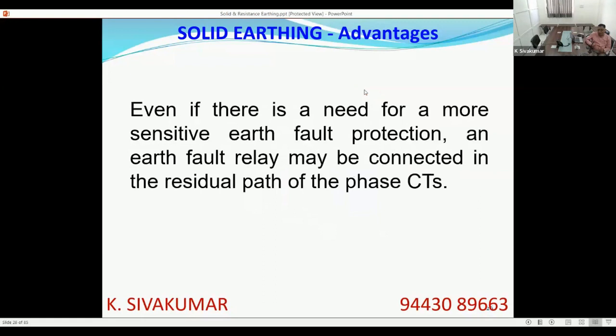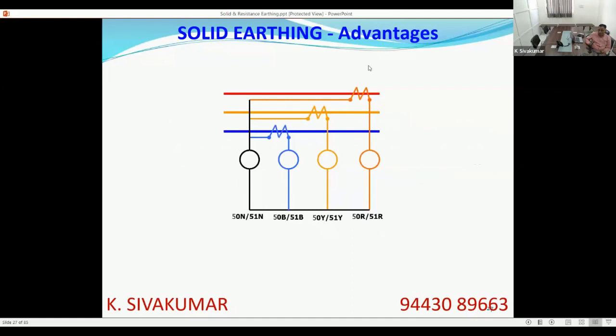Suppose you still say that you need a better, sensitive earth fault protection. You can provide an earth fault relay in the residual path. This is the most common practice in industries. People use 3 overcurrent elements and 1 earth fault element. You can provide an earth fault element with a sensitivity of say 10 to 40% or 20 to 80%.